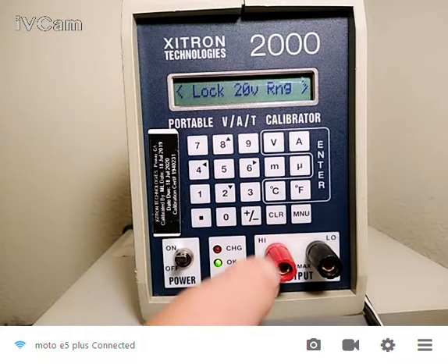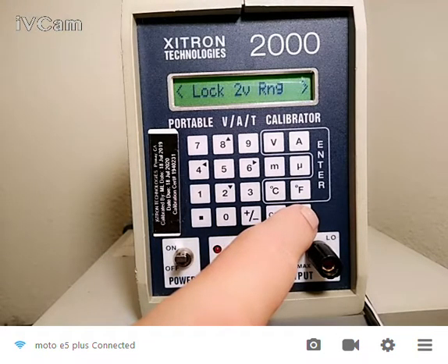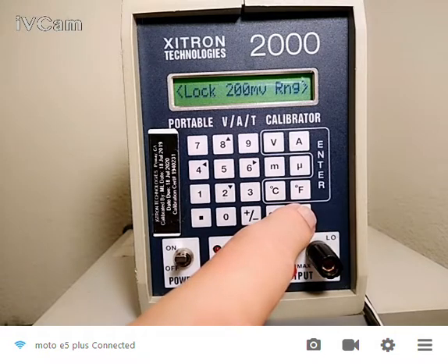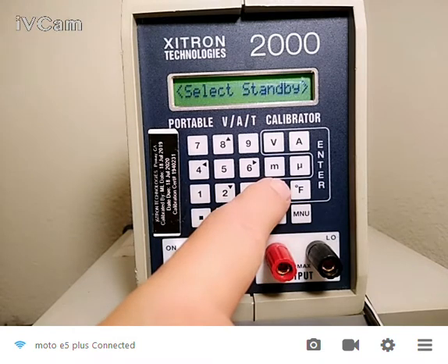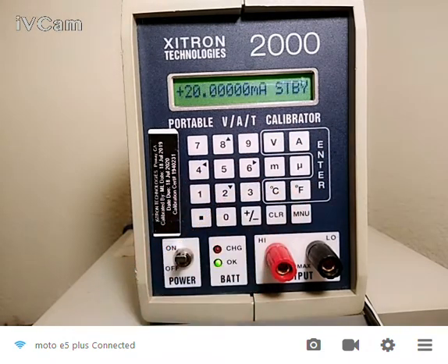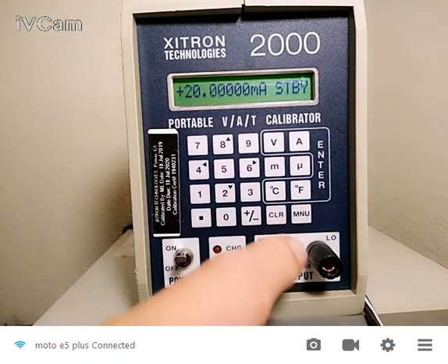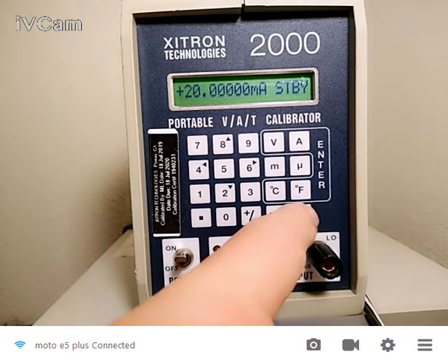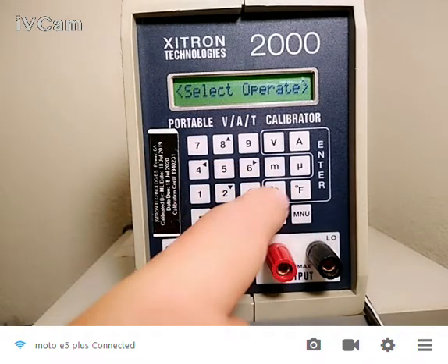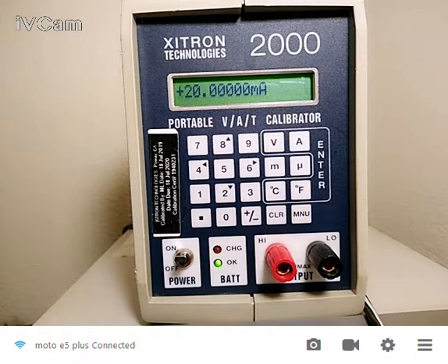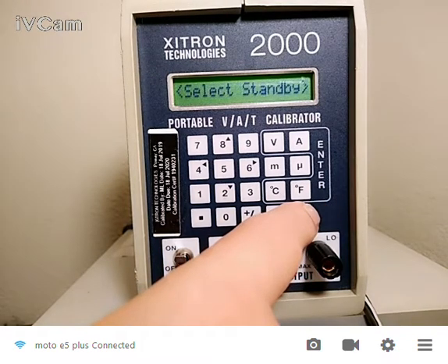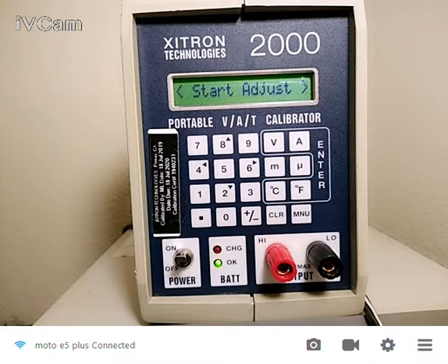So if I hit this menu button right here, I can see my choices. Let me see, I want to start at the beginning. And that's select standby. So if I hit enter, any one of these enter buttons, now you can see that I'm in standby mode. What that does is it turns the output on and off. And now when I hit menu again, the first choice is select operate, and I'm back to operate. So that's standby. Adjust allows me to slew my output either high or low.